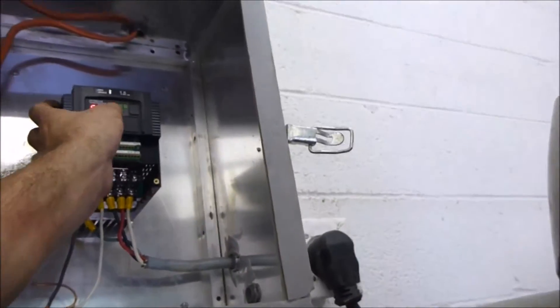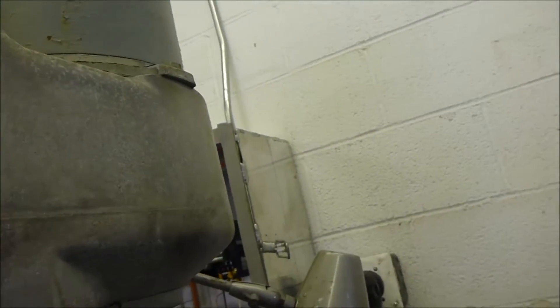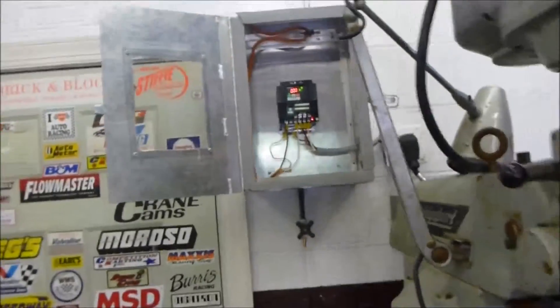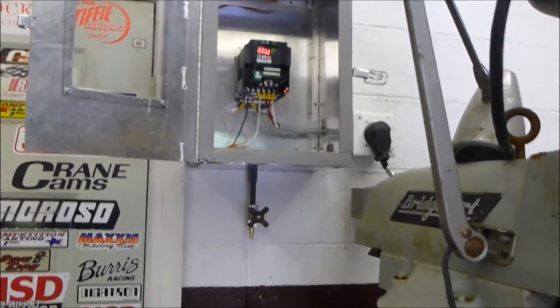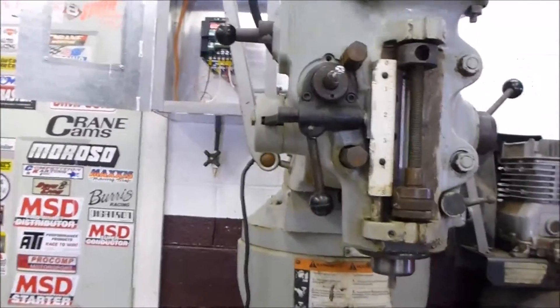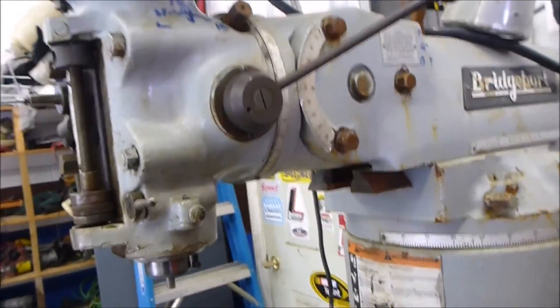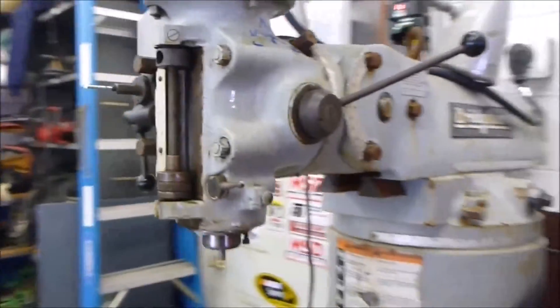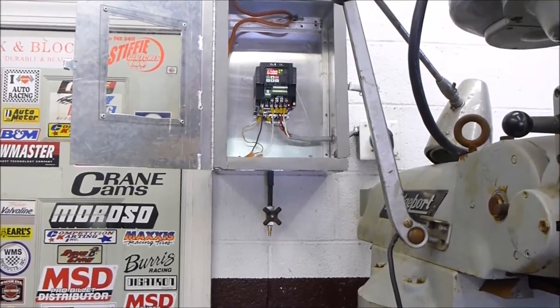Turn it off. I'll turn it back on. I can then adjust. Since I don't have my remote panel set up yet, this is going in the high speed. One thing I did find is that connected the way that it is, when I use my speed range lever over here, when it's in the high speed, it is spinning in the proper direction. When it's in the low range, it's spinning in the opposite direction, spinning the way it's not supposed to go. So that's where I had to go ahead and rewire my VFD to have it going in the right direction.